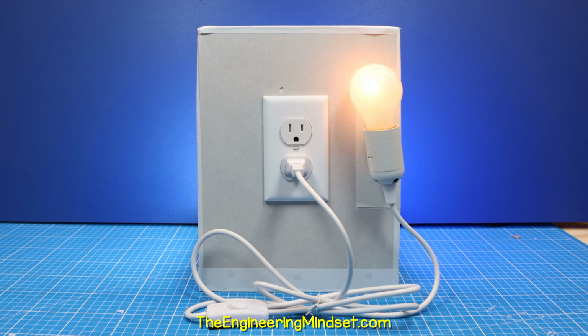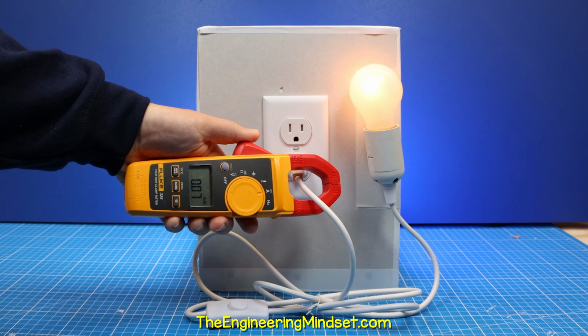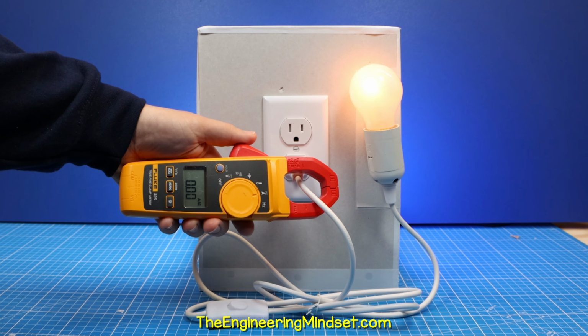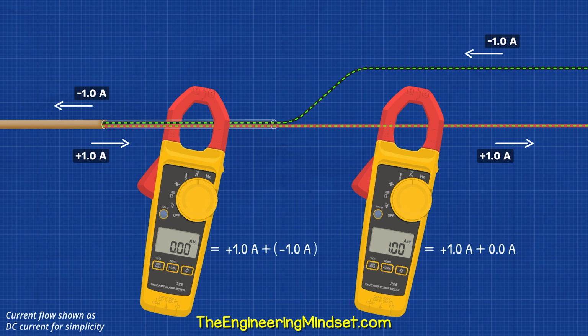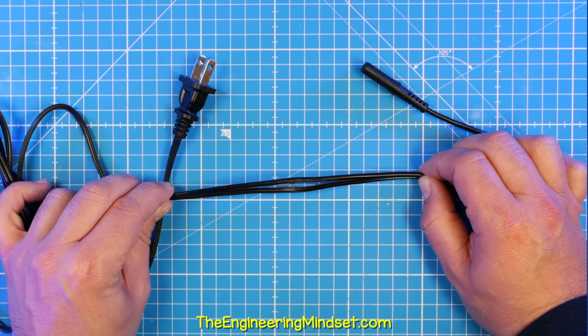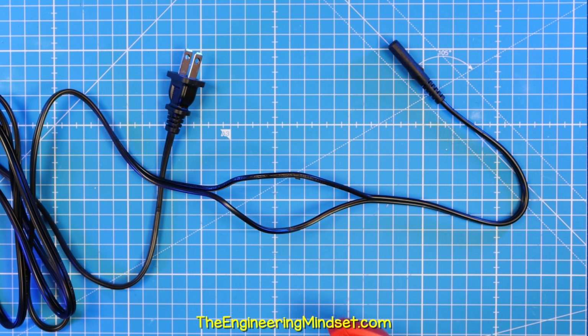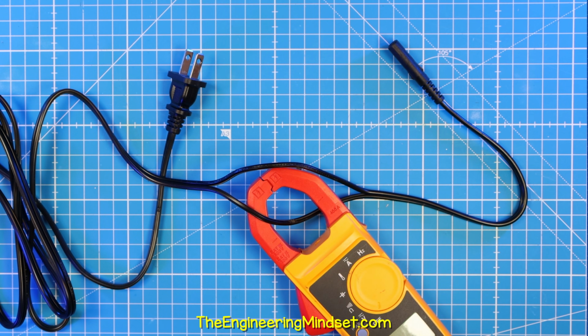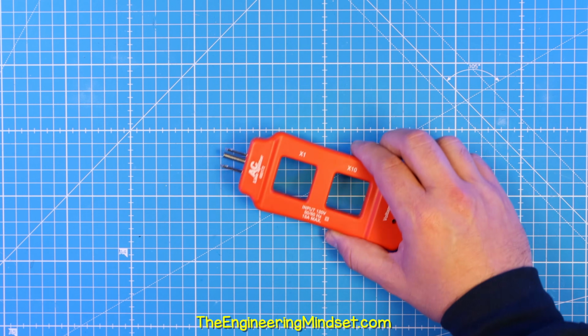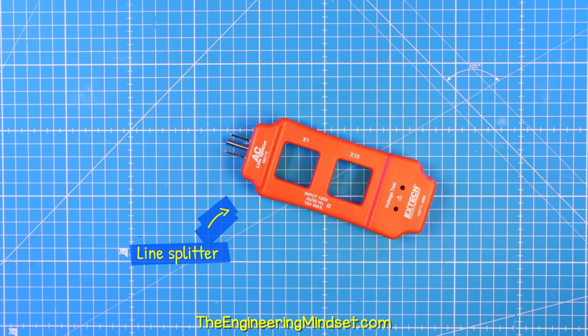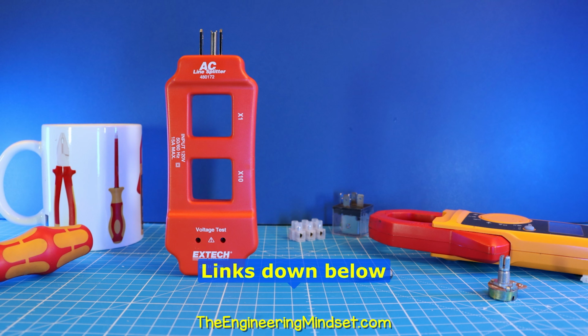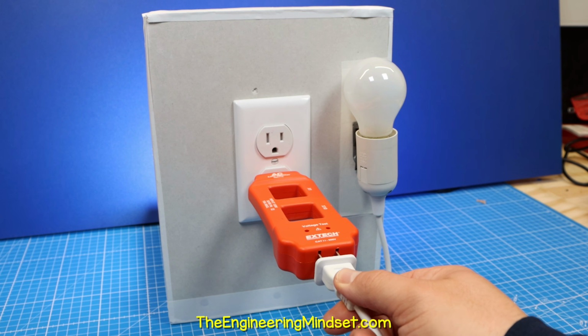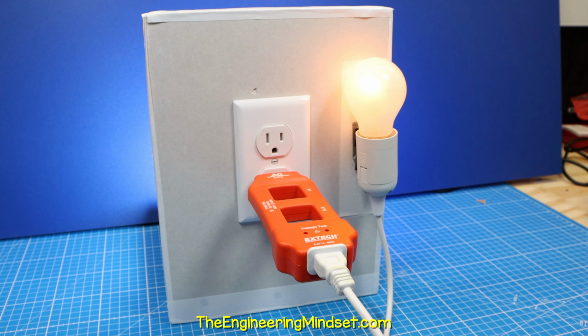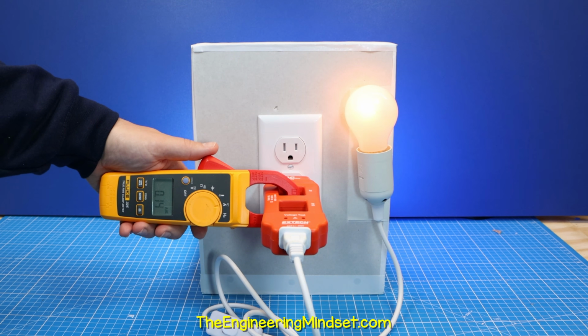This lamp is clearly on. It has AC current flowing through it. But if we clamp the power cord, the meter will read 0. That's because the hot and neutral will cancel each other out. So we need to separate the wires. We can only clamp one at a time. A much easier and safer way is to use a line splitter like this. I'll leave a link down below for you. We just plug this into the outlet and then plug our appliance into it. And then we clamp around the device to read the current.